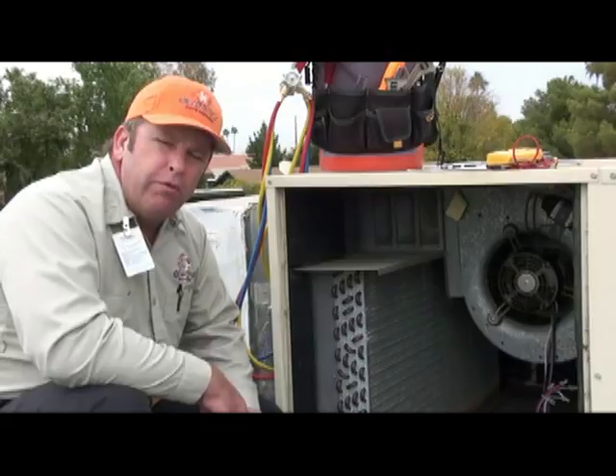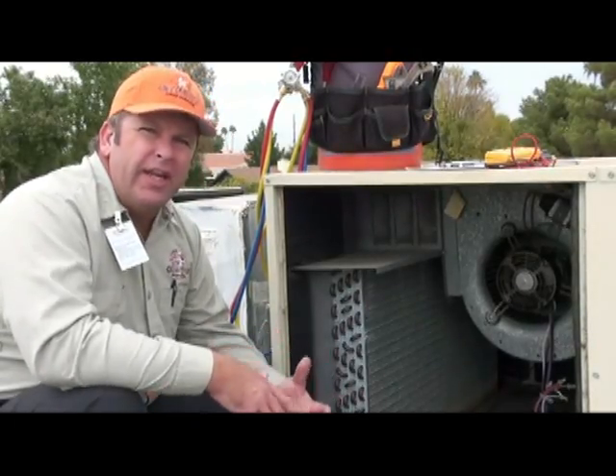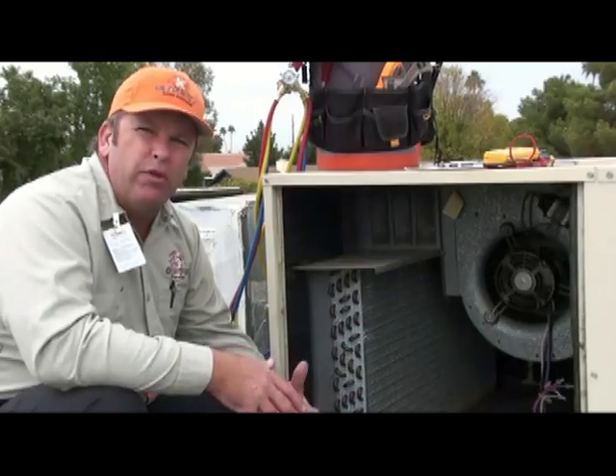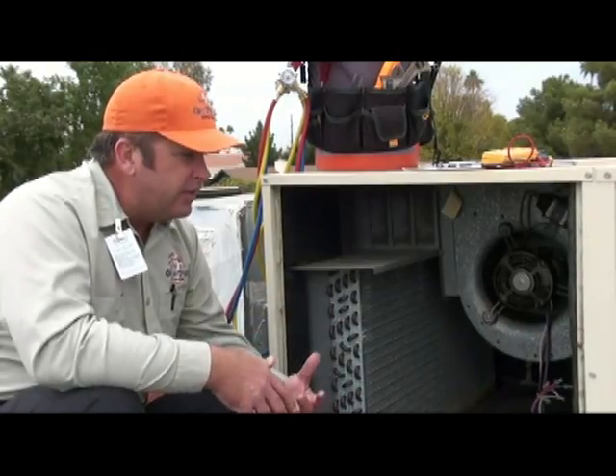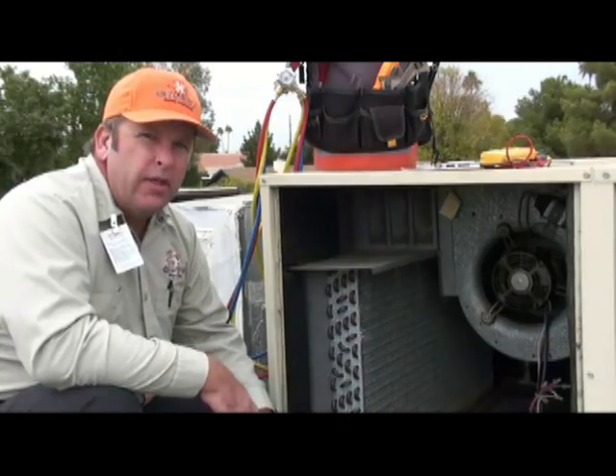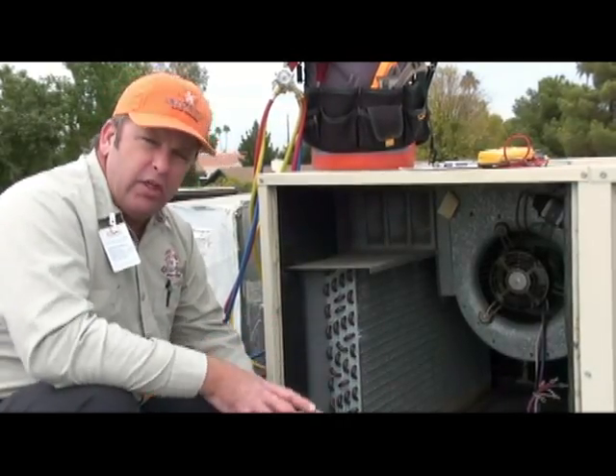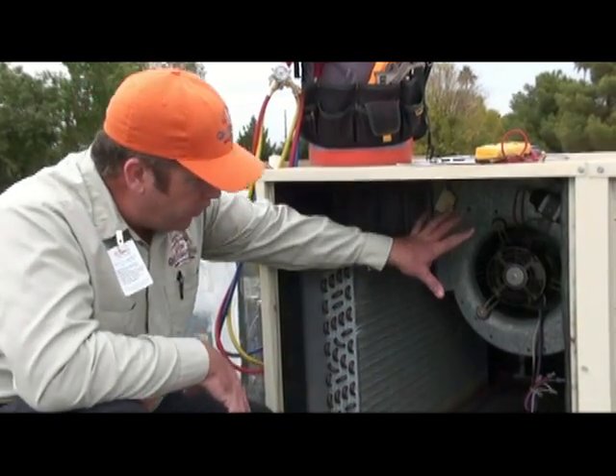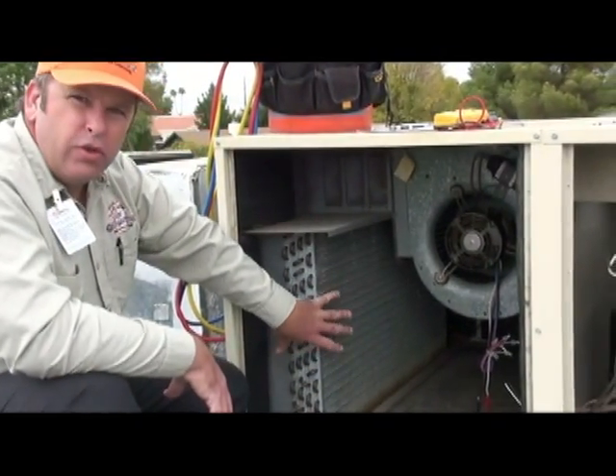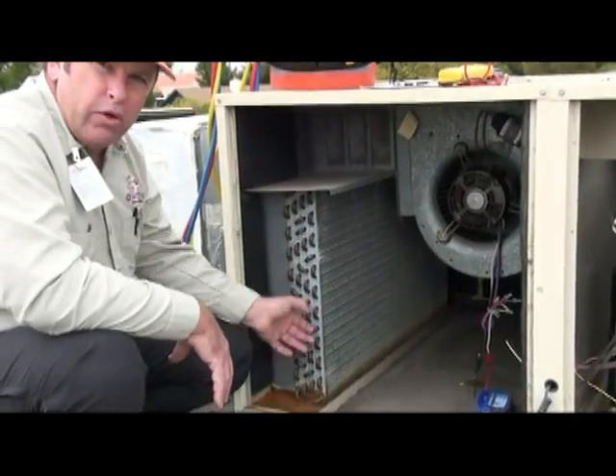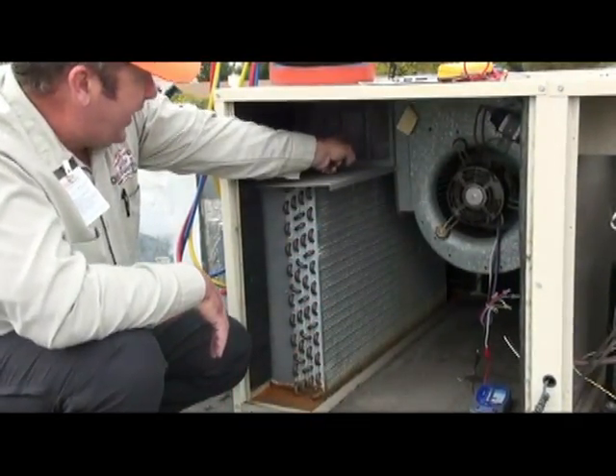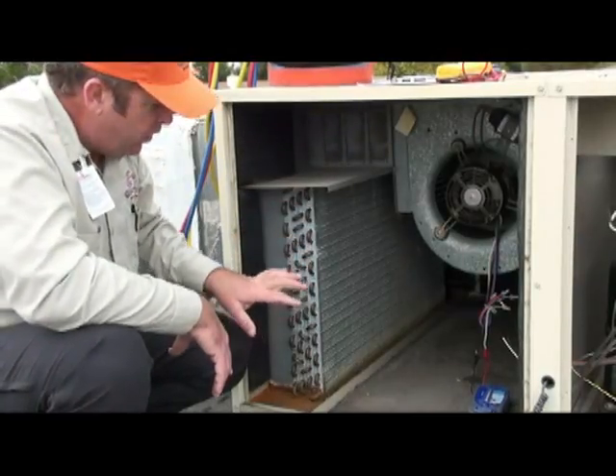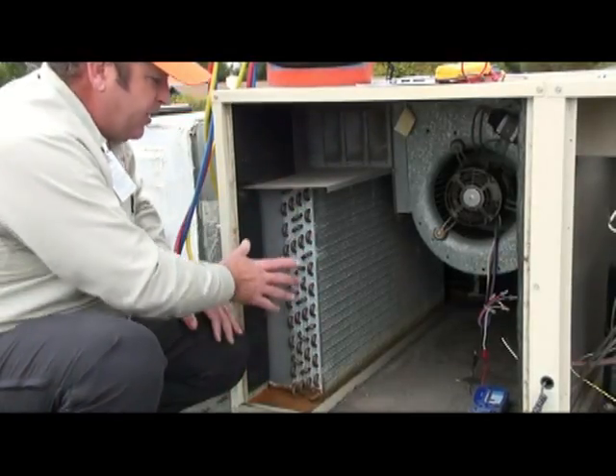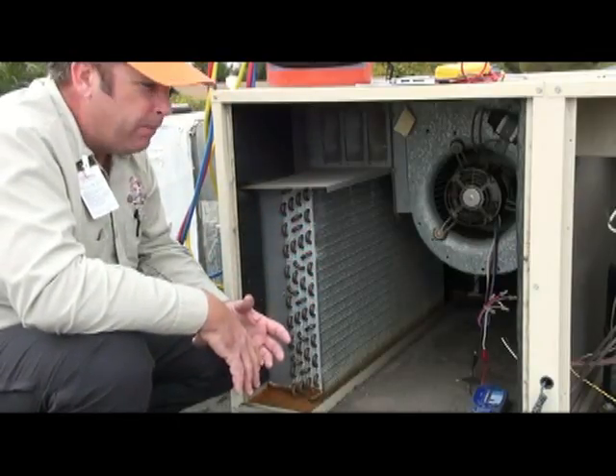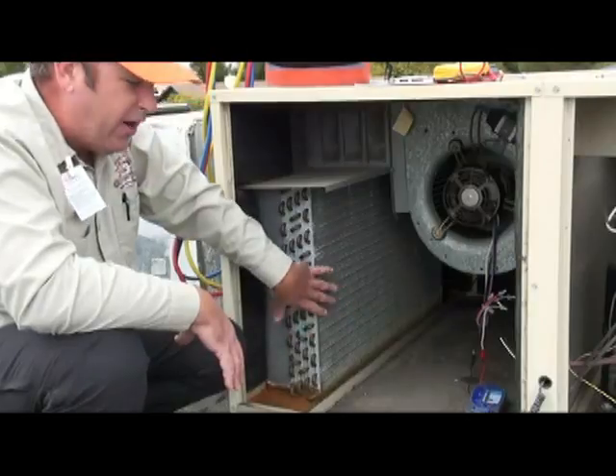One of the last failure modes of the blower motor is going to be overheating. Now, overheating can be caused by several different factors inside the system. One of the most common factors of overheating is just general maintenance within the unit. This motor has to pull air across this coil in order to heat or cool the home, and then it pushes the air back into the house through the supply registers. What happens is if this coil gets plugged up with dirt, this motor is not able to pull air efficiently or effectively across this coil.